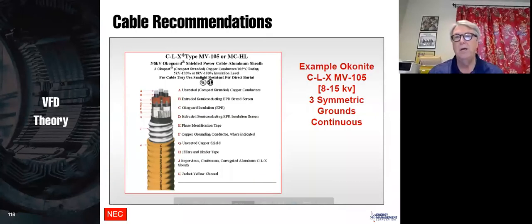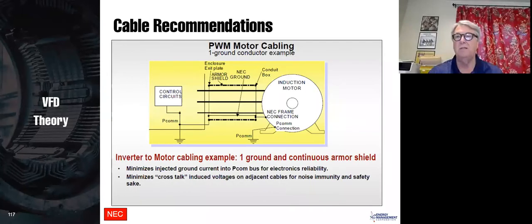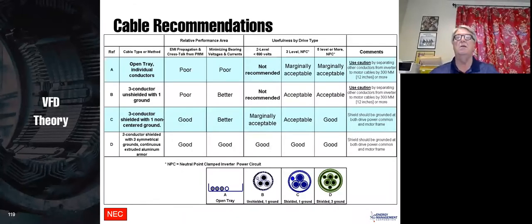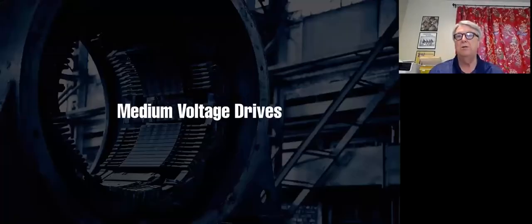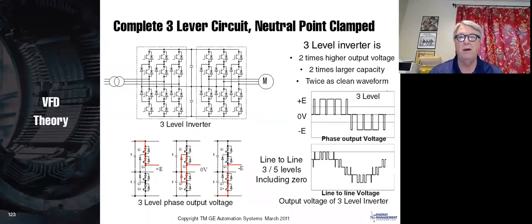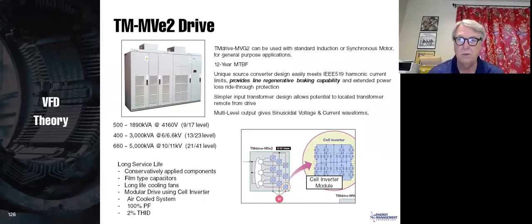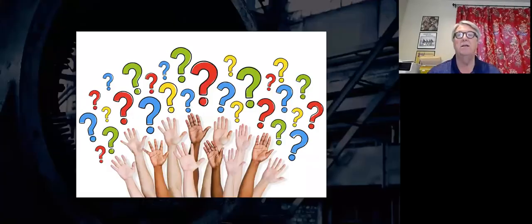There's some more pictures. That's medium voltage VFD insulation, and this is a table which is very good. This is from TMEIC, Toshiba Mitsubishi-Electric on their medium voltage motors, but it also has one for low voltage motors, and it tells you what cables are acceptable going from your variable frequency drive to your motor. So I'm going to stop here. There's some other stuff on medium voltage drives, but we're going to have a special class on medium voltage drives, and so I'm not going to cover that today. So I am done, and I'm turning the time back to Tyler.